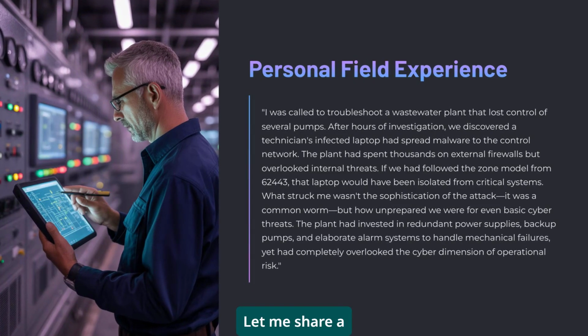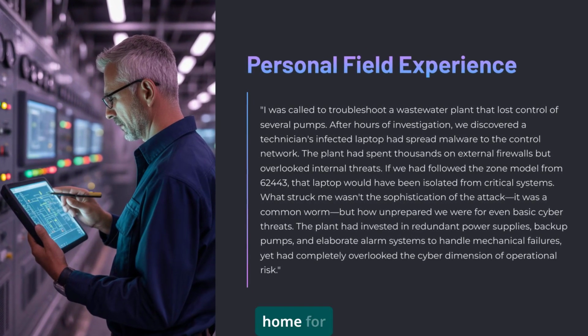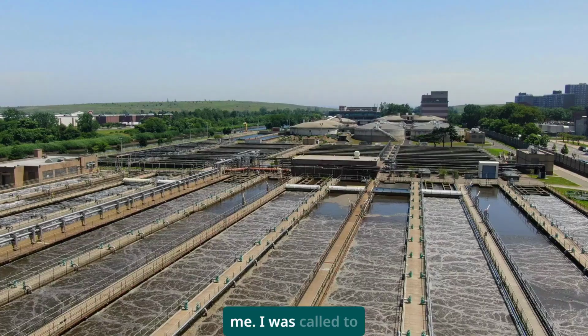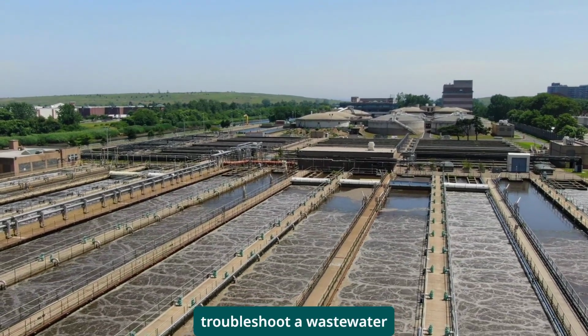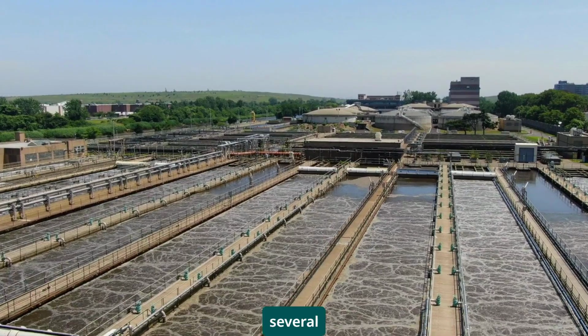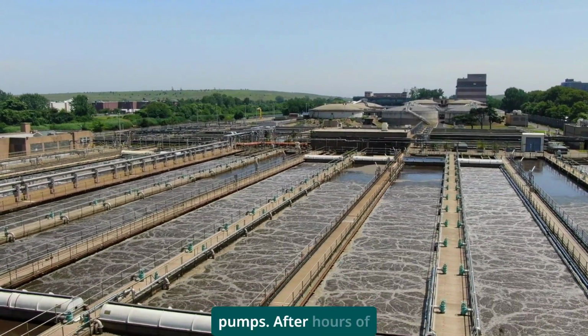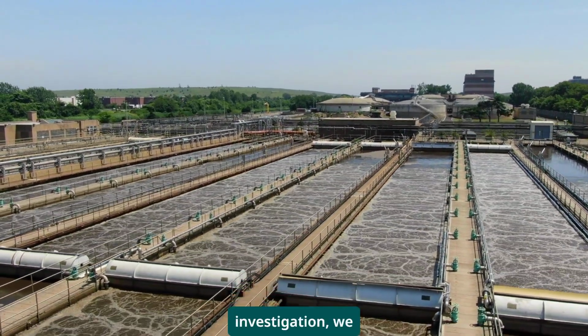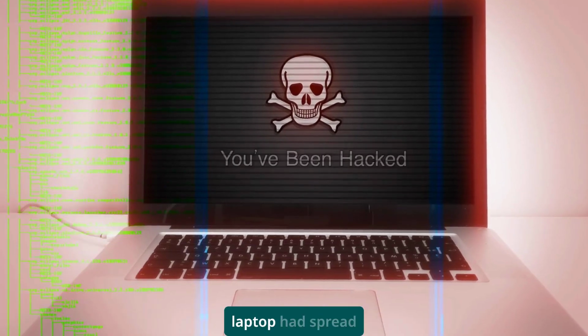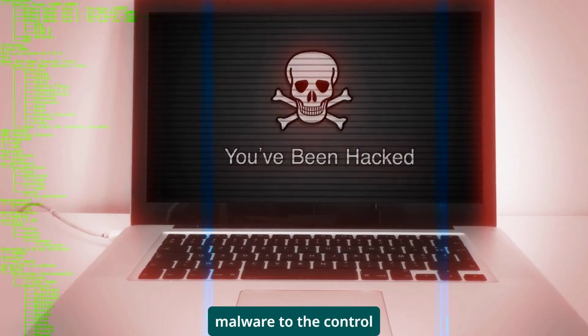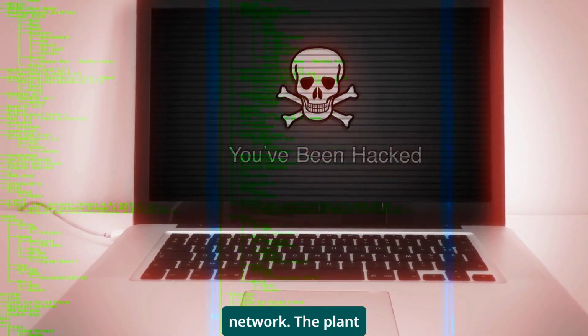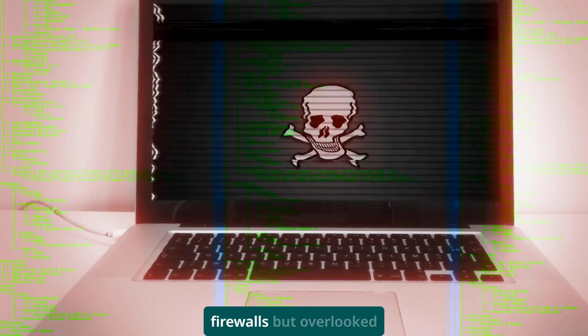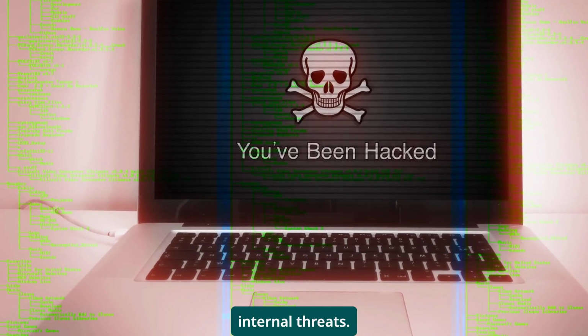Let me share a story that really drives this home for me. I was called to troubleshoot a wastewater plant that lost control of several pumps. After hours of investigation, we discovered a technician's infected laptop had spread malware to the control network. The plant had spent thousands on external firewalls but overlooked internal threats.